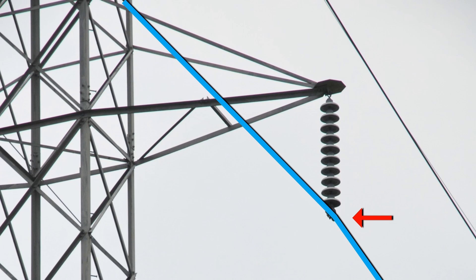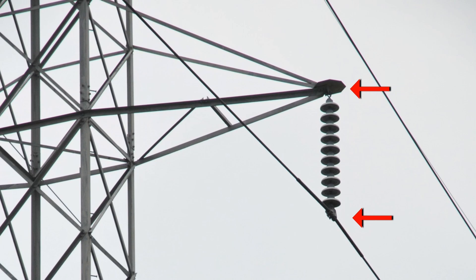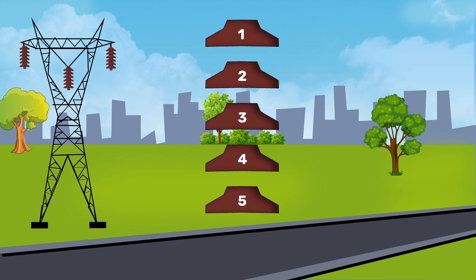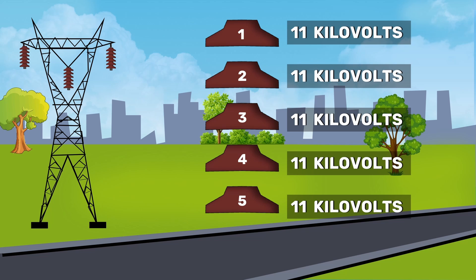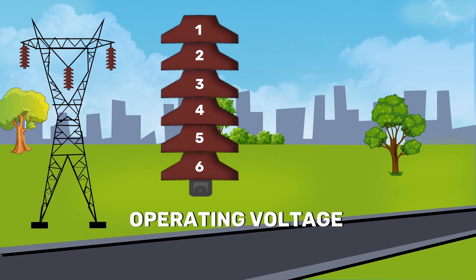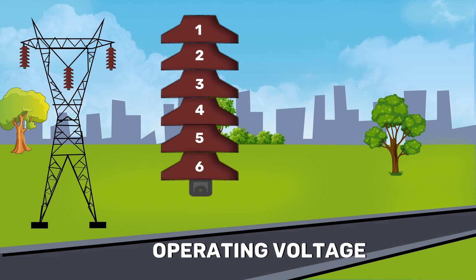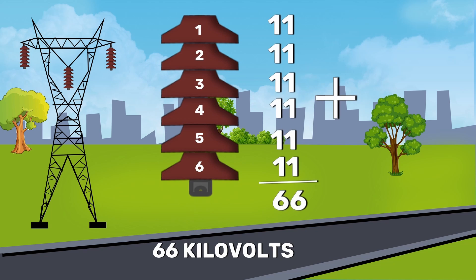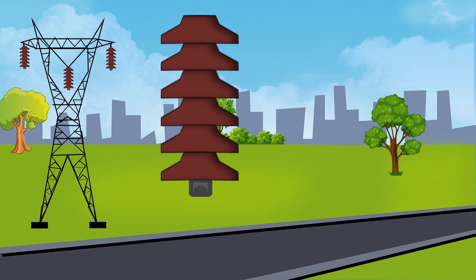The conductor is suspended at the bottom end of the string, while the other end of the string is secured to the cross arms of the tower. Each disc is designed for a voltage rating of 11 kV. The number of discs in a series depends on the operating voltage. For example, if the working voltage is 66 kV, then 6 discs in series will be provided on the string. If one disc is damaged, it can be replaced with a new one.